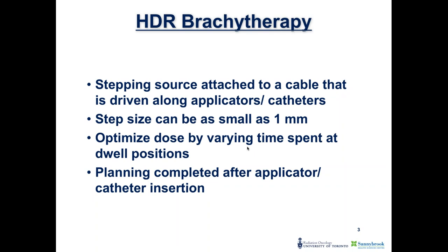HDR brachytherapy is different from LDR in that it uses a stepping source, which is attached to a cable that's driven along applicators or catheters. The step size varies depending on the particular manufacturer and equipment, but it can be as small as one millimeter, so it can be very precise in how we deliver dose. We optimize dose by varying the time that the source spends at each dwell position.